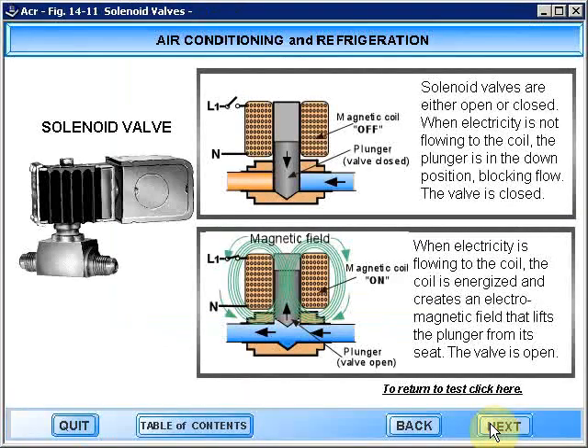Solenoid valves are either open or closed. When electricity is not flowing to the coil, the plunger is in the down position, blocking flow. The valve is closed. When electricity is flowing to the coil, it is energized and creates an electromagnetic field that lifts the plunger from its seat. The valve is open.